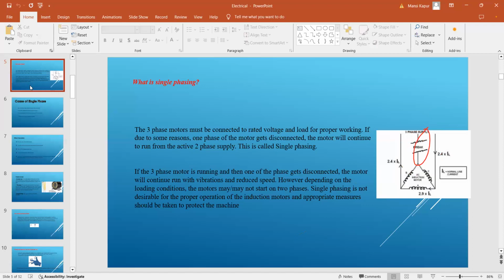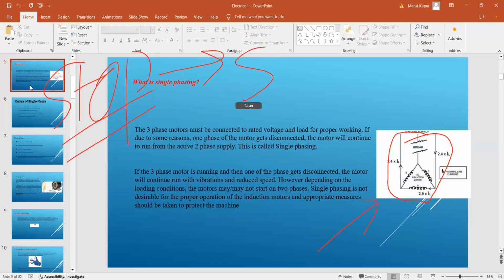The motor will continue to run with the two active phases. Why does it continue to run with two active phases? Because we have the insulated earth system on board the ship, right? Yes, sir, insulated neutral. That I will also tell you, just wait a few more minutes. I will tell you what is insulated and what is neutral. This is called single phasing. So if single phasing is occurring, it might be possible that your motor keeps on running. But if you stop this motor and start it again, is it going to start?